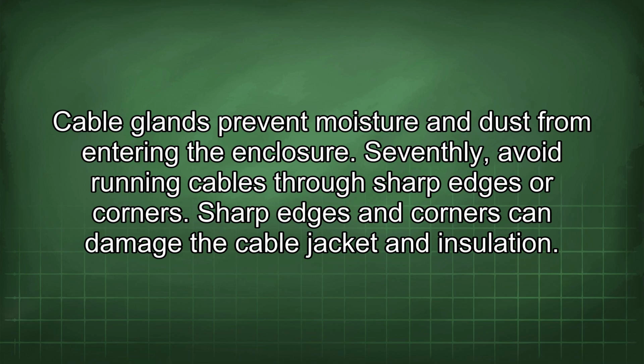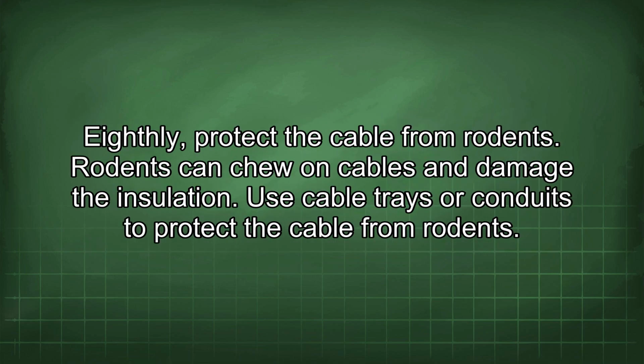Seventhly, avoid running cables through sharp edges or corners. Sharp edges and corners can damage the cable jacket and insulation. Eighthly, protect the cable from rodents. Rodents can chew on cables and damage the insulation. Use cable trays or conduits to protect the cable from rodents.